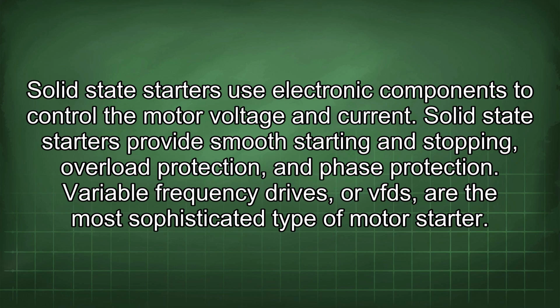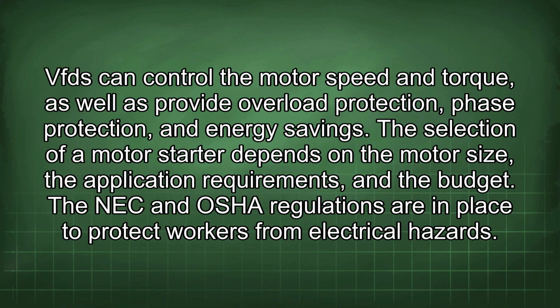Solid-state starters provide smooth starting and stopping, overload protection, and phase protection. Variable frequency drives, or VFDs, are the most sophisticated type of motor starter. The VFD can control the motor speed and torque, as well as provide overload protection, phase protection, and energy savings. The selection of a motor starter depends on the motor size, the application requirements, and the budget.